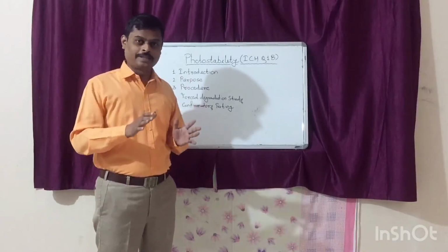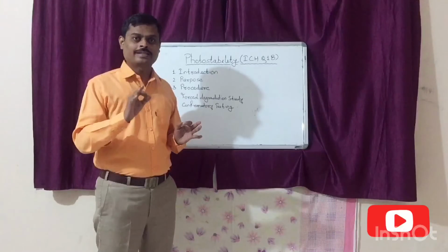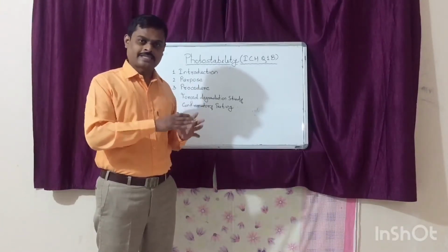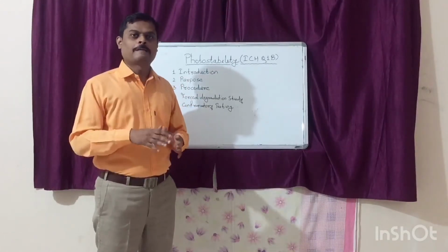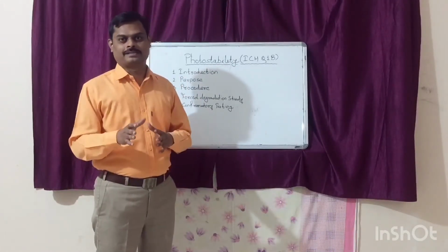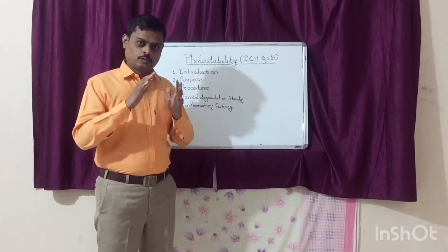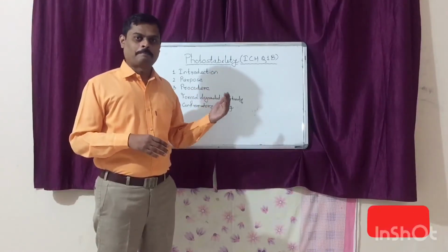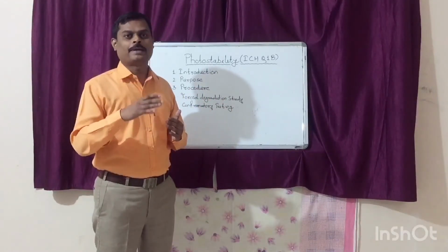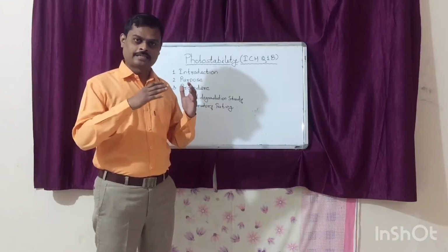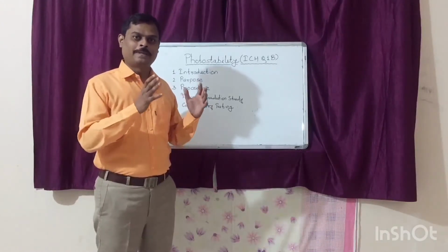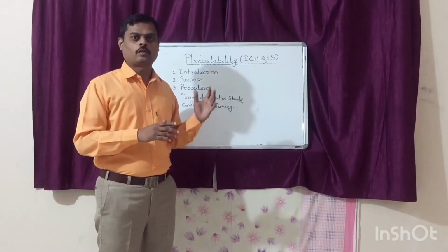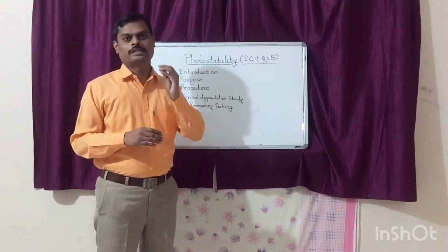However, the suitability of your light resistant packaging should be assessed or evaluated based on the photostability studies. Your photostability studies should indicate that your packaging, that is light resistant packaging, is effective enough to mitigate or to minimize the effects of light on the quality of your drug substance or drug product.